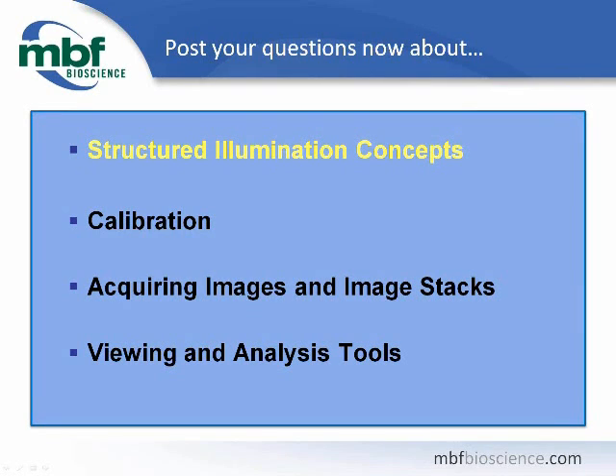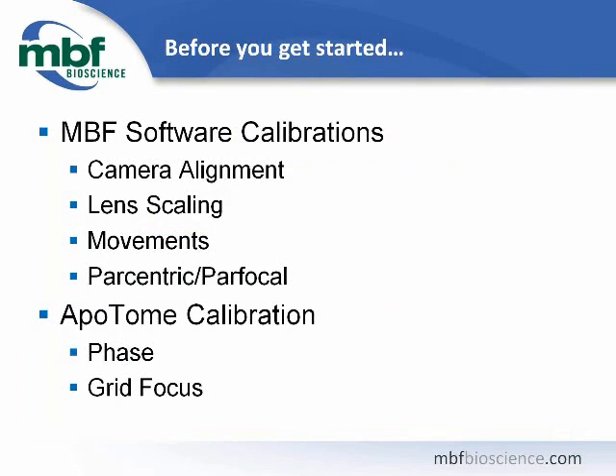Please feel free to continue submitting questions. Before you get started, there are a number of things you need to ensure. First, all the software calibrations required for normal use of Stereo Investigator or Neurolucida are required. You need to ensure your camera is aligned, your proper lens scaling is set, the movements of your stage are correct, and that you have performed par-centric and par-focal calibration.